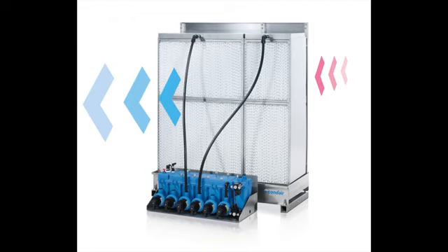Now, if this is useful, like in a hot factory, then it's a really nice bonus, and you can help lower cooling costs. But often we're humidifying places in the winter, and this is because indoor air is much drier then, and this isn't the season we normally need more cooling. So in fact, cooling from a cold water humidifier will often need to be counteracted rather than enjoyed. So evaporative or spray humidifiers operating in the winter inside an AHU will need some form of heating before the humidifier. Now, this makes the air warm enough to be able to accept moisture from the humidifier, and also ensures it's at the correct supply temperature after the evaporative cooling effect.